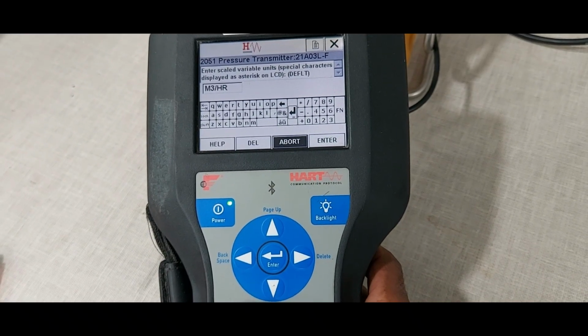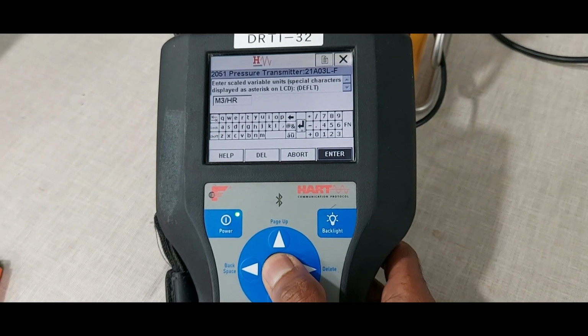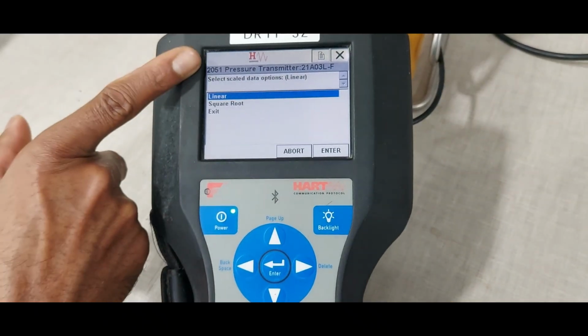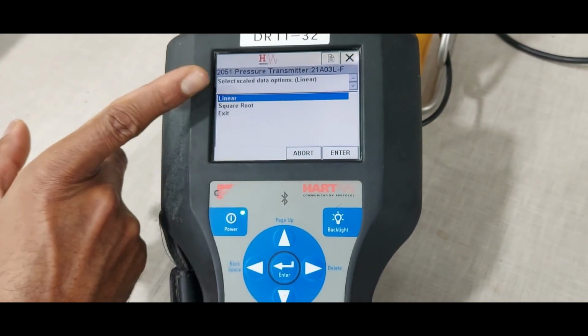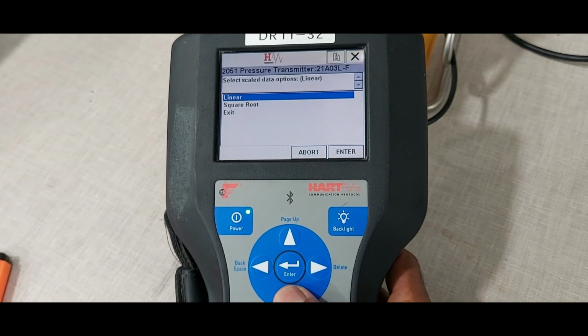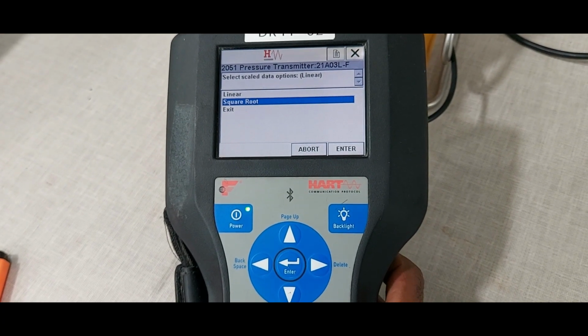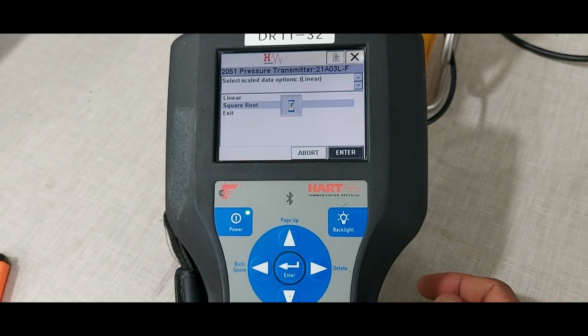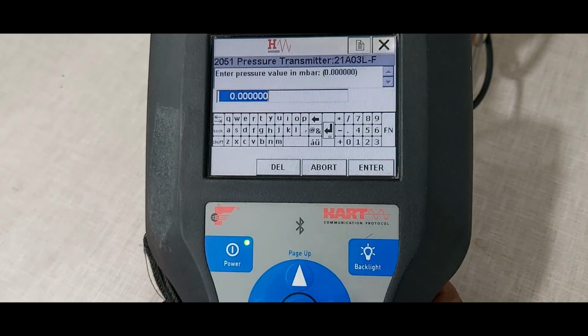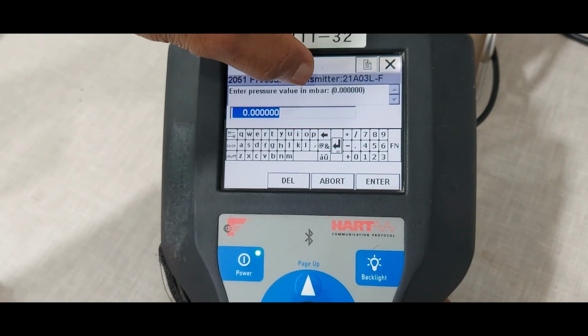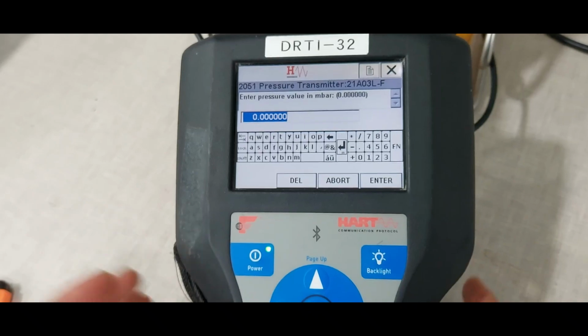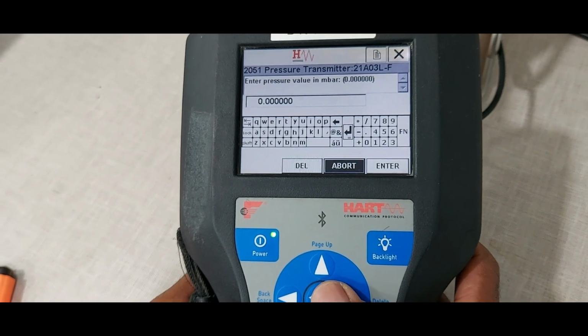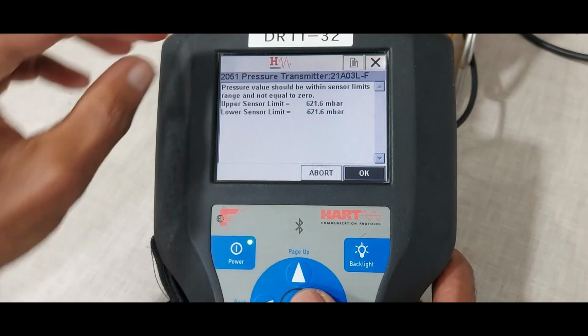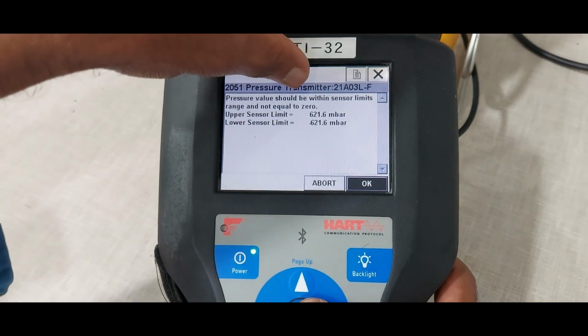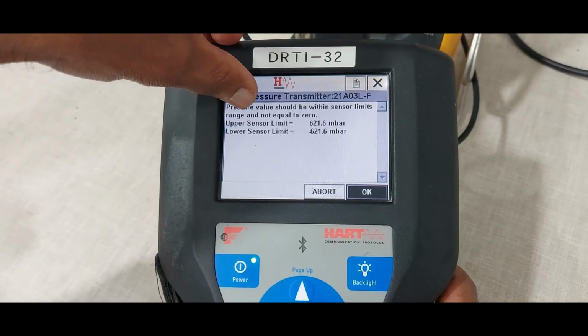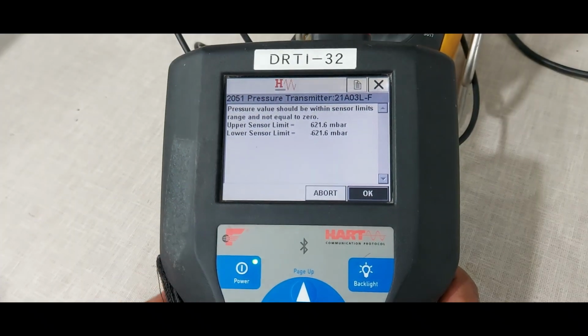Okay, next enter it. This is a flow unit. Select the scale data options, linear or square root. Actually, the flow transmitter is a square root condition. We selected the flow square root. Enter it. Enter the pressure value in millibar. Zero conditions, actually 0 is 0. Pressure value should be within the sensor limit range, not equal to 0. Then okay.